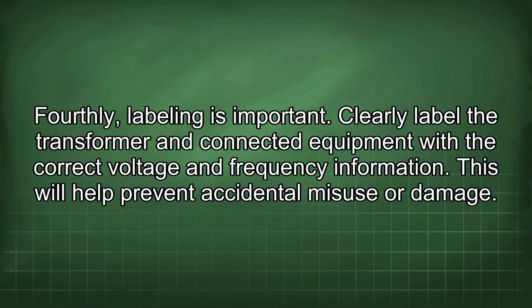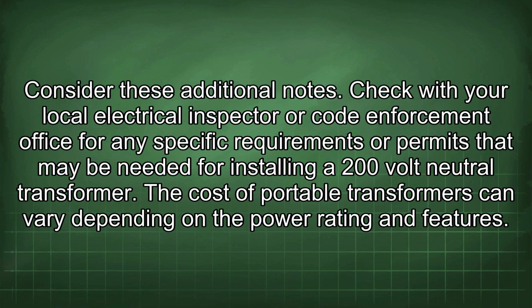Fourthly, labeling is important. Clearly label the transformer and connected equipment with the correct voltage and frequency information. This will help prevent accidental misuse or damage. Consider these additional notes. Check with your local electrical inspector or code enforcement office for any specific requirements or permits that may be needed for installing a 200-volt neutral transformer.